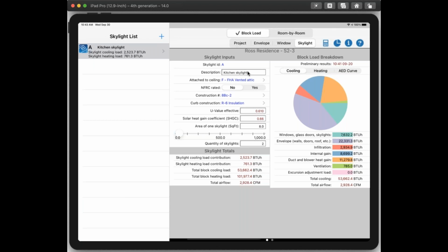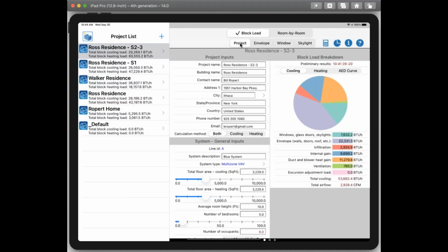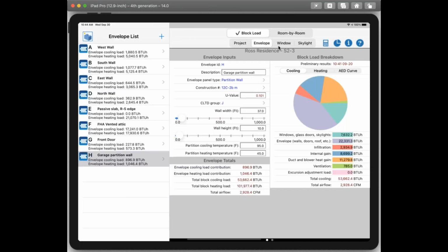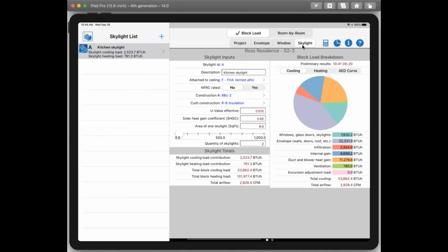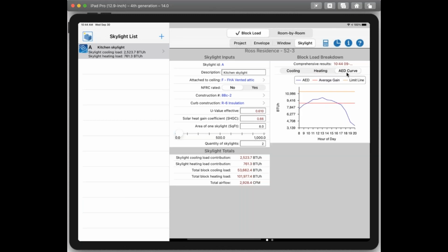So based upon all of these inputs that I've just entered, meaning my project, my envelope inputs, my window, and my skylight inputs, I now have a block load. My block load is this value here, 52,000 BTU per hour, which is around 4.5 tons. And then here's my airflow. My heating load, about 101,000. And here's my AED curve. Now you can see that my AED curve changed a little bit, probably based upon the changes I made when I was demoing this. And now my peak is below this limit line.